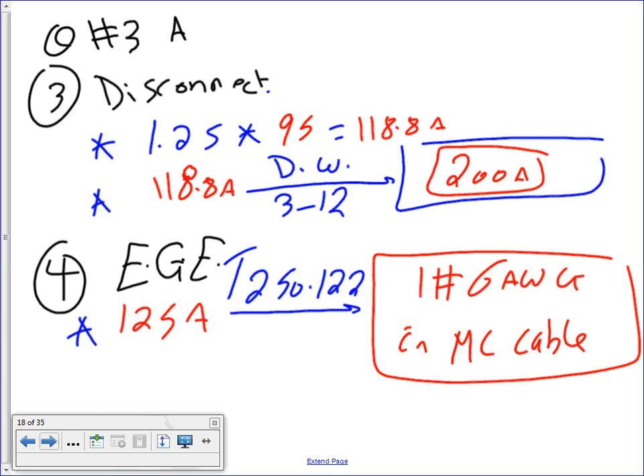It makes more sense if we're using conduit and wire, then we have to size it and pull it. If it's a cable, the equipment ground conductor comes sized by the manufacturer, almost based on these rules. So either minimum or even larger, they put it. Larger is good. So 200 amp, the next largest disconnect. Yes, over 100. Yep. They don't do 150, unfortunately. Yeah, 200 amp. If you're in doubt on the test, 200, they have 400 and 600, 800, and then 1200, and then I can't remember after that where it goes.